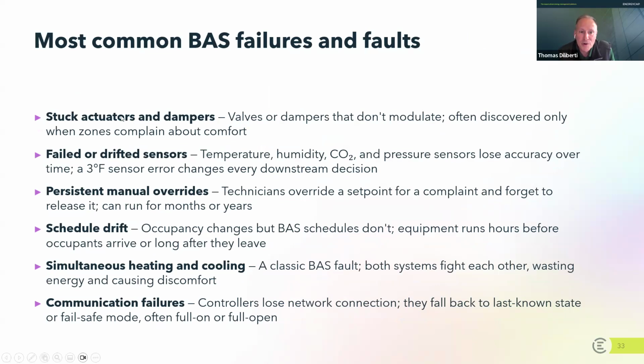So many times you learn these things by looking at the screens. You sit behind the building automation system and you see valves that are giving you inconsistent values or dampers that just don't seem to be closing properly because of temperatures. But a very common phenomenon of failure is failed or drifted sensors. So yeah, temperature is supposed to be reading 70, but the sensor's showing 67, so it's drifted by more than a couple degrees, so it's creating other problems downstream. Overrides, people overriding the system. Schedule drift, again, schedules just get stretched out because occupants keep coming and going, and rather than schedule it more consistent with how people occupy the space, people stretch it out.